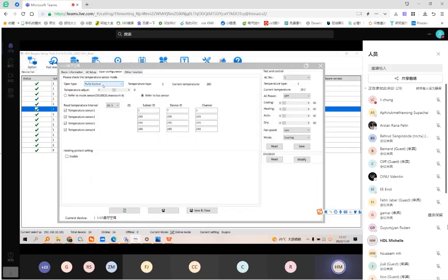So if you select the AC to do the fully control, it will manage the operation of all of it. So that's the fully control. Now I select the AC as fully controlled. So when I do configuration for the panel, then the panel must be in slave control. And here, you can adjust the temperature as well. So if you find the temperature are not the same, and here are some gap between the temperature, you can adjust the temperature from here to make some temperature compensation.